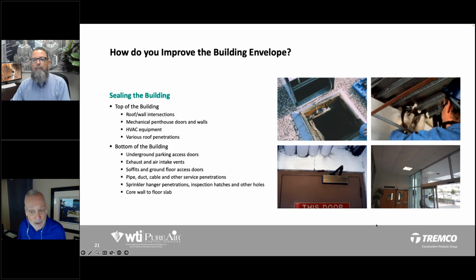The top left picture there is a roof exhaust. When we flipped it back, we were looking at a drop ceiling, and all of a sudden we have an 8 square foot hole on top of this chimney, basically. Normally the designer brings the roof up to the curb, and the mechanical contractor drops in his ducting and leaves a 2-inch gap. Sometimes it's flashed over, but it's never sealed. You get enough of those at the top of the building, and it's a huge hole right where stack pressures are the greatest.